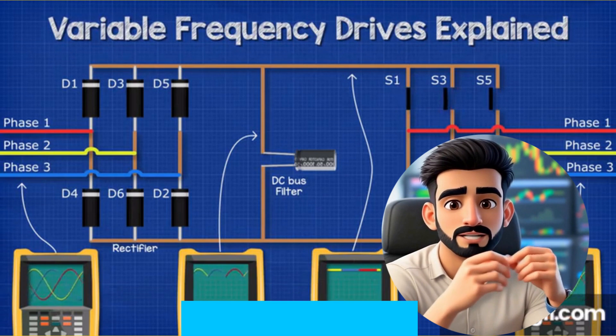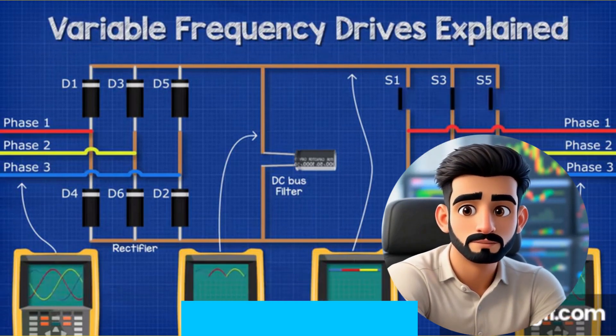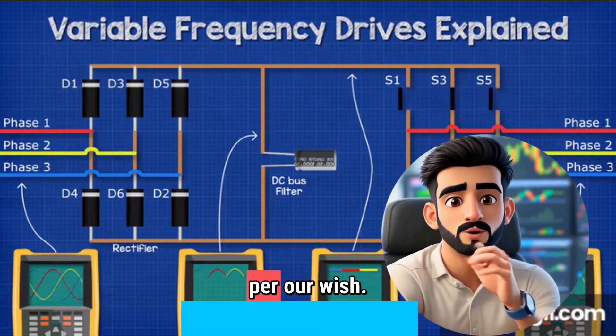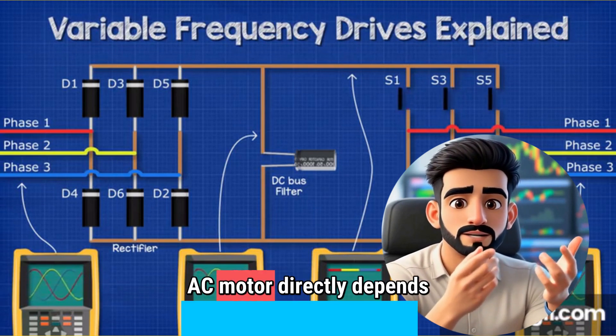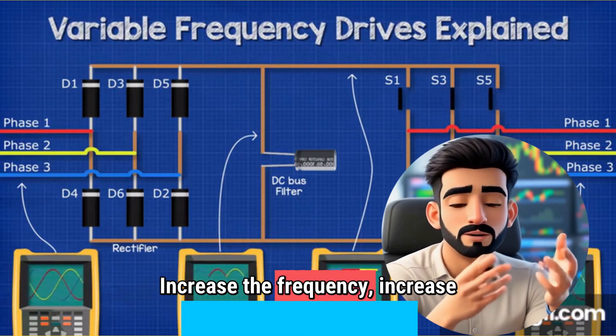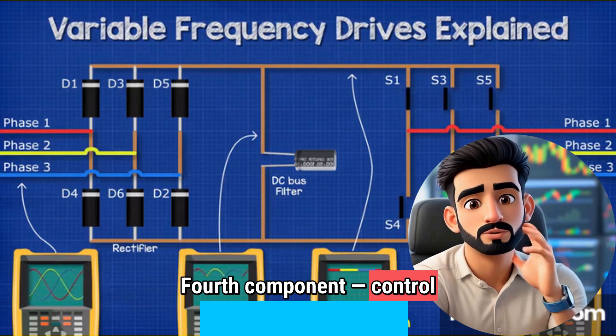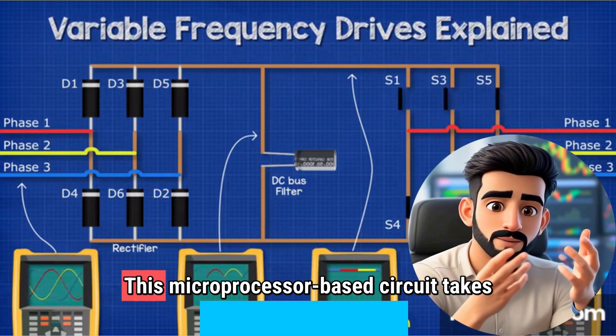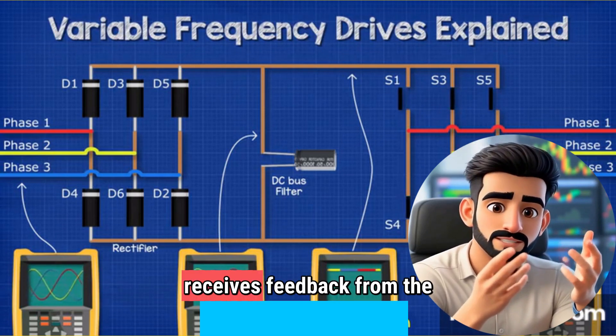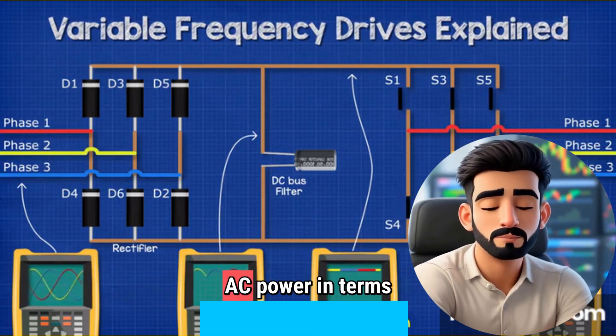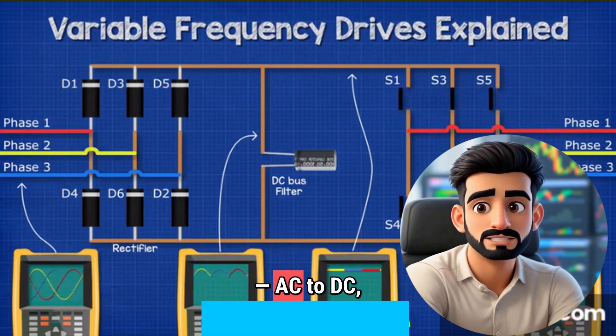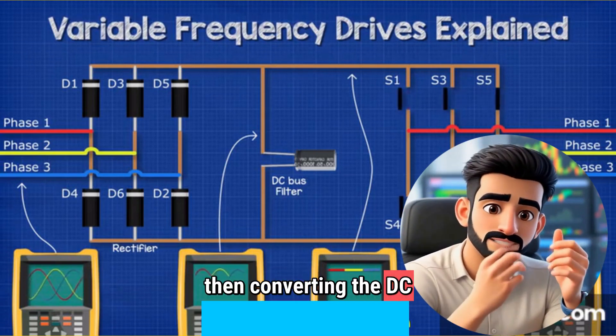You can call the inverter the heart or magician of the VSD. The inverter takes that smooth, stable DC power and converts it back into AC power — but here is a twist. The new AC power generated is not normal AC power; the frequency and voltage of this AC power can be controlled as per our wish. And as we know, the speed of an AC motor directly depends on the frequency it receives: increase the frequency, increase the speed; decrease the frequency, decrease the speed. The fourth component — the control circuit — is the brain of the VSD. This microprocessor-based circuit takes commands from the user, receives feedback from the motor, and guides the inverter on how much AC power, in terms of frequency and voltage, needs to be generated for the required speed of the motor. The overall process is: AC to DC, smoothing the DC, and then converting DC to controlled AC to power the motor.